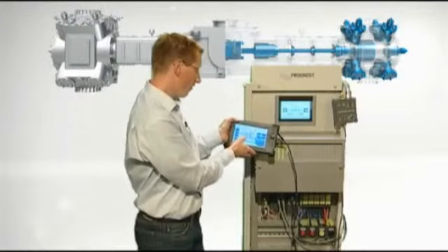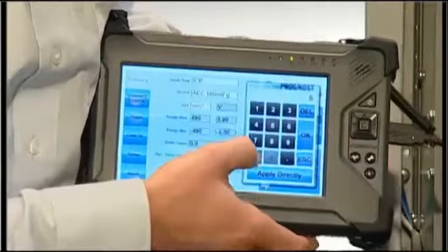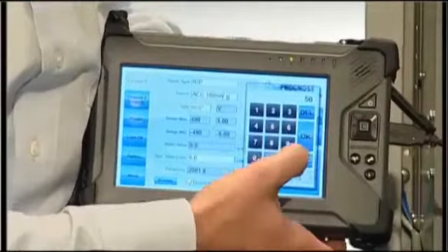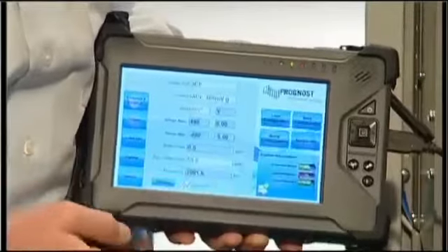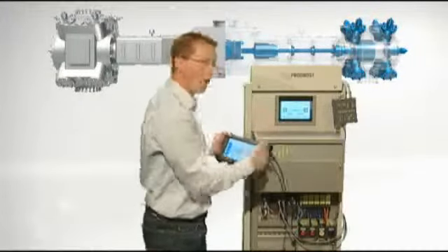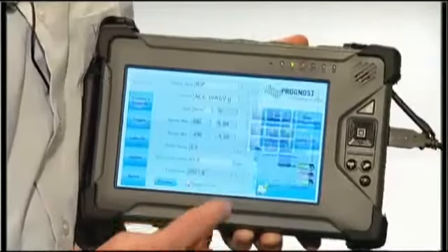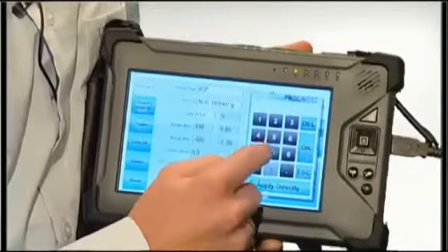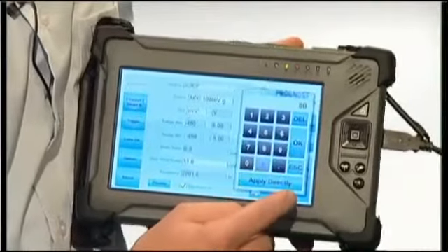We will now change the value from a dynamic RMS value from, say, 50 in a first go. We apply it directly, and we will see 50 meter per square second on screen. The signal, the sensor we now drive into the protection rack, is simulating 50 meter per square second. Now let's go and violate the safety limit, slowly increasing to those values that are most applicable.